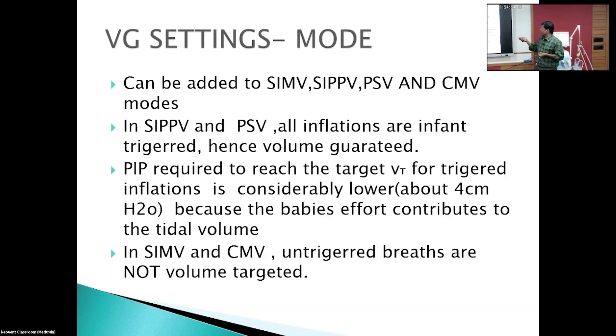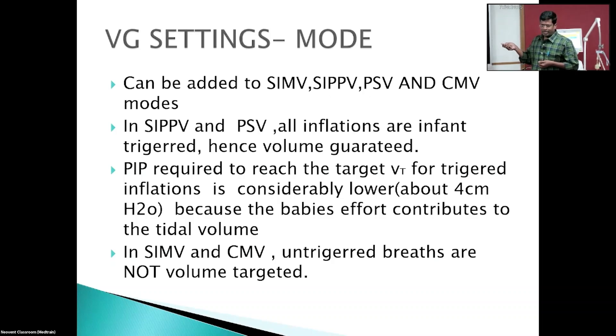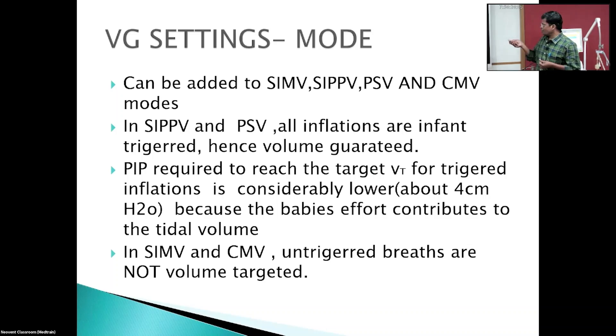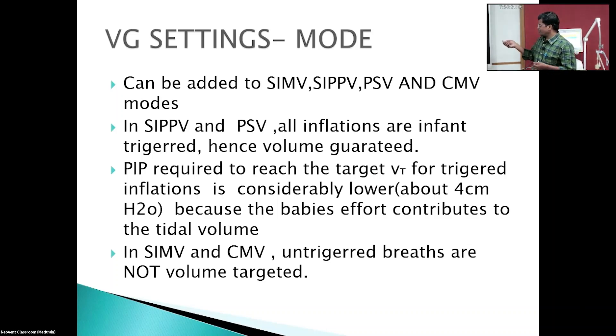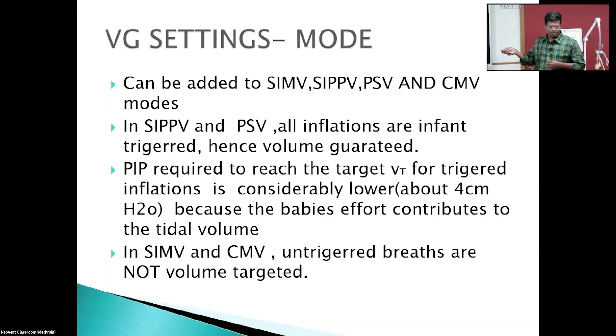The basic modes compatible with volume guarantee are SIMV, SIPPV, PSV, and CMV. In SIPPV and PSV, all breaths triggered by the baby will be supported by the ventilator, making these ideal modes to add VG. The PIP required to reach the target volume for each triggered inflation is about 4 cmH₂O lesser than non-triggered inflations, because the baby's effort contributes to achieving the targeted tidal volume.